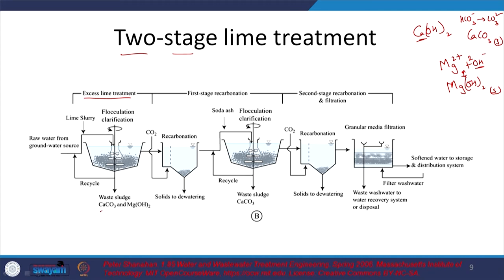So that's why we have precipitation of both CaCO3 and magnesium hydroxide. As we know, to remove magnesium hydroxide, the pH has to be considerably high, around 11, 11.5, depending upon your relevant system. So it's a bit too high, right? And I don't need this high level of pH. And also now I'm done with removing magnesium, but I added calcium because in this lime, I have Ca2+ and 2OH-, right? So 2OH- was consumed by magnesium, but I added calcium.